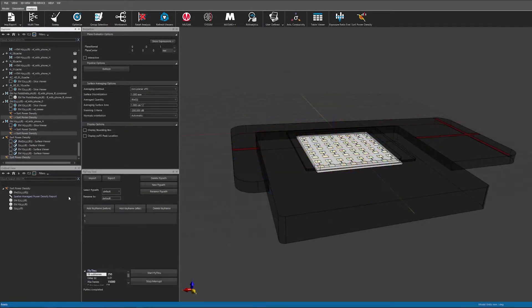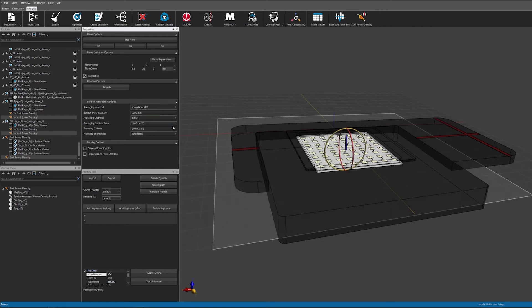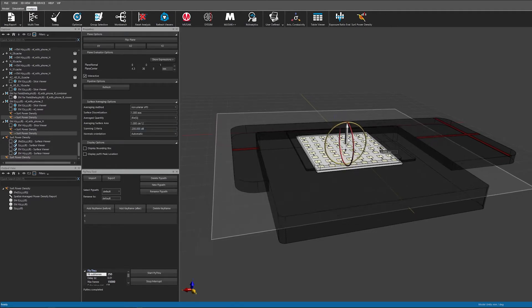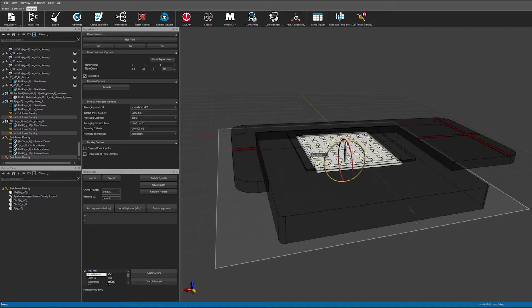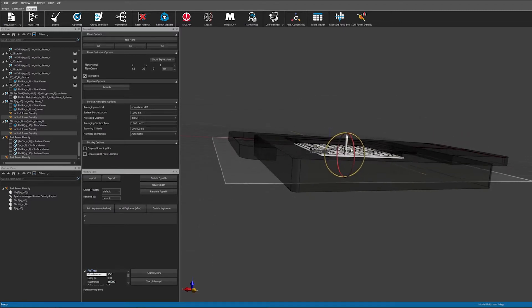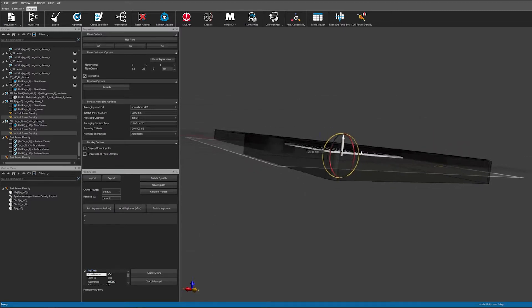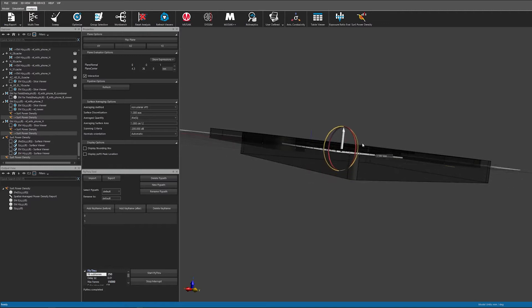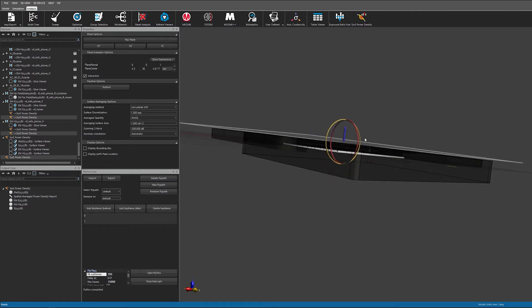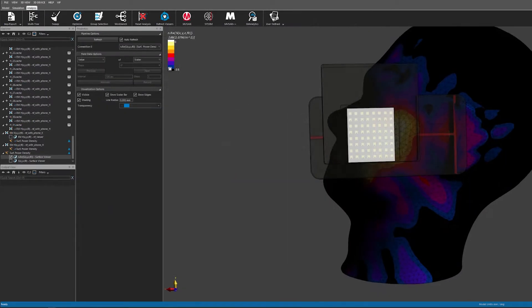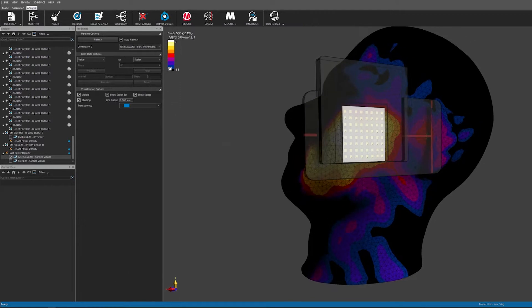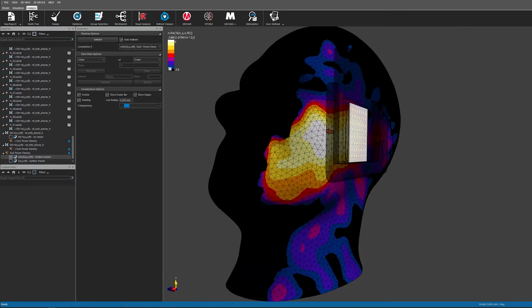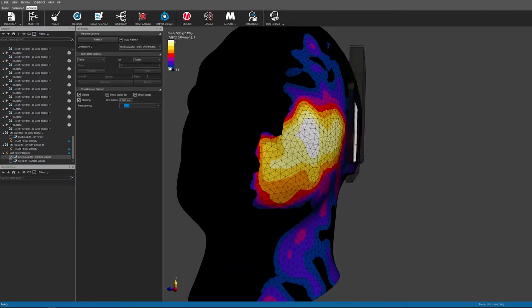The new power density evaluator is compliant with the very latest draft of the IEC IEEE standard and is very easy to use. I can define evaluation surfaces using an interactive tool which is convenient for planar surfaces or from CAD objects like the SAM head here.